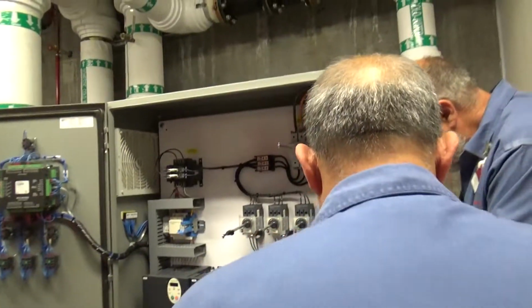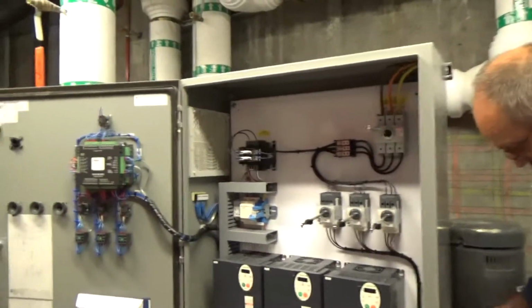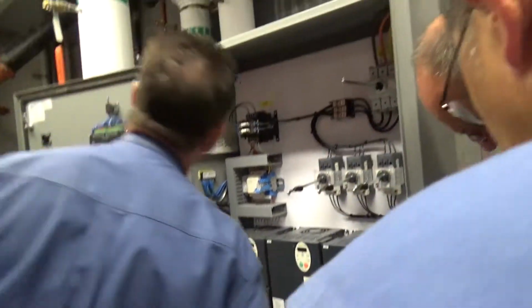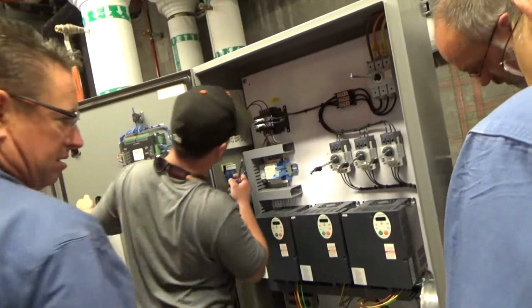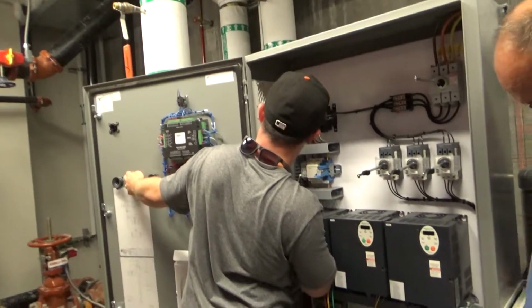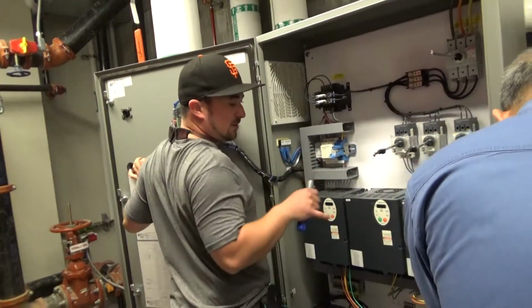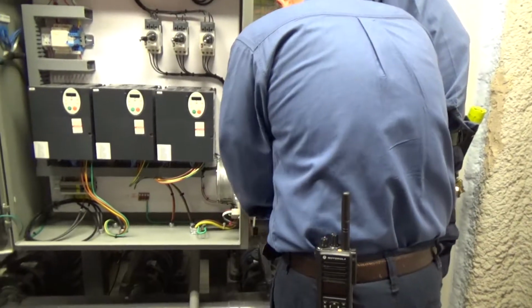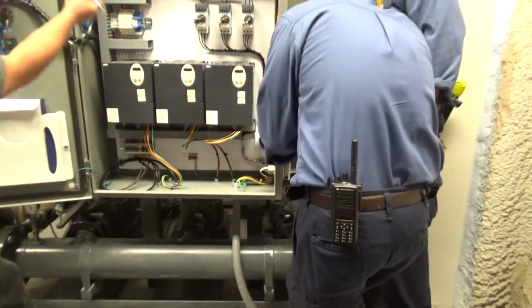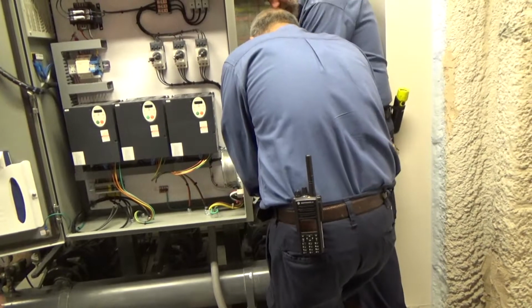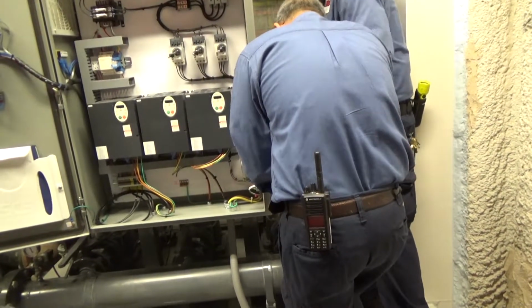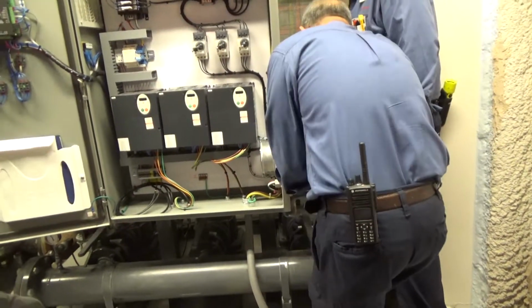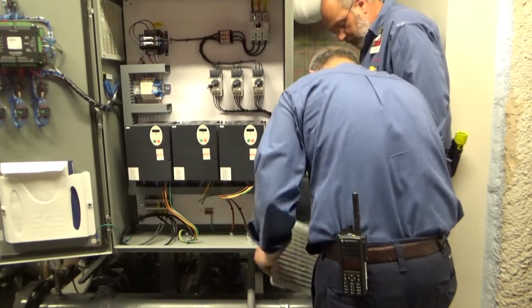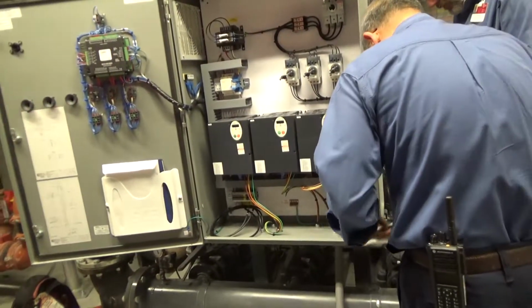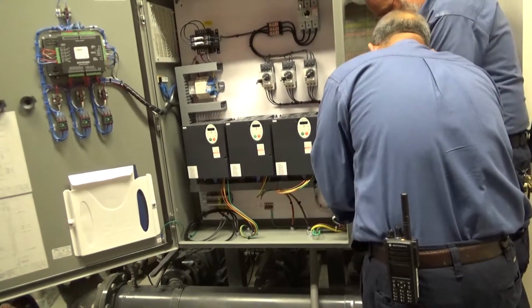So just to note, there's 2 filters, right? There's a filter on there too. No, it's just on your intake. But I mean, I see it right there. There is a filter in this line as well. That's a first. Interesting. Okay. I don't know why. They must have used the same one on the intake and outtake, because usually there's never one on the exhaust. Well, you're pulling in and you're pushing out, so why would you need a second? If it's standalone, when the fan's not running, air could be circulating the other direction. That's true. But like I said, usually you never see that. So you guys have 2 in there, so keep that in mind. Order 2, have 2 on hand.